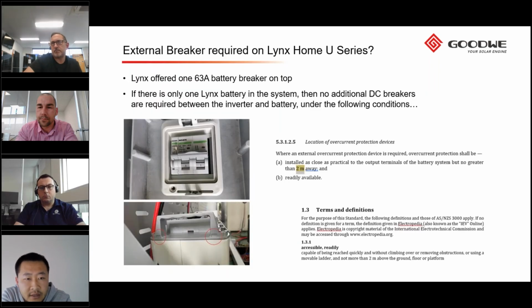And then the next one is our Lynx battery. So basically on each battery, we have a 63 amp battery breaker on top of the battery. If the installer just uses one battery linked with the inverter, and the gap between the inverter and the battery is less than 2 meters, then you don't need to install an external DC breaker between the inverter and the battery, purely because our battery comes with this breaker as well, and this breaker can be accessed without using any tool to open the top cover of the battery.